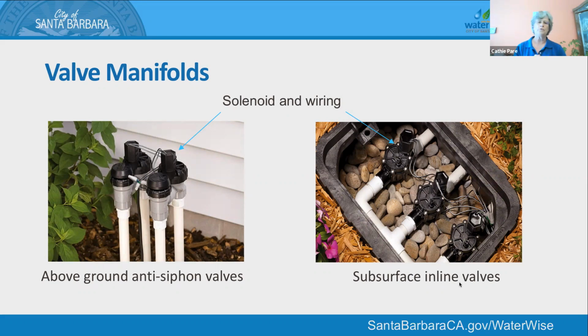And that's where the water runs through. It's a good place to look if you're having problems with controllers not working. Make sure that the wire nuts holding the wires are actually dry and in a silicone nut, because those inline ones, it's like being in a bathtub. So water and electricity, they don't play well together. Next slide.